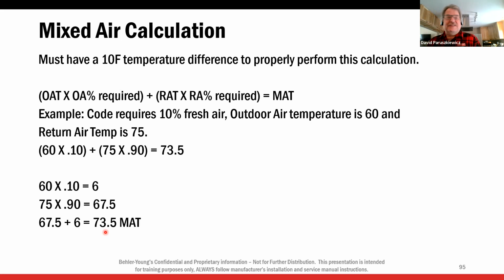Now, I know a lot of guys leave it at the factory defaults. That is not correct. So I calculate this out. I put my probe in my mixed air by my blower, and I'm going to adjust my minimum position until I have 73.5 in this example. All right. Now, if I have a 2-stage blower, I'm going to have to run high speed and set it, and low speed and set it, because they're different. And what you're going to find is that at low speed, the damper is actually going to be further open physically than on high speed.